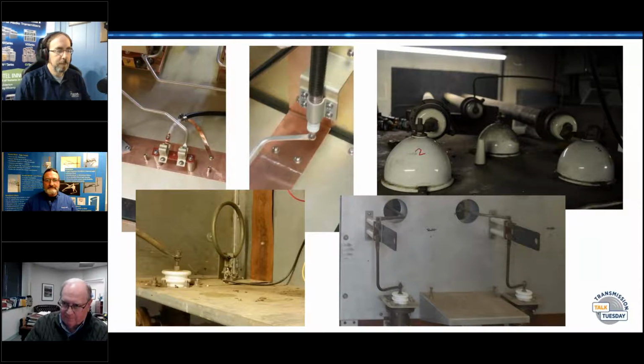That's why threaded connections inside ceramic insulators can sometimes cause trouble, because the sharp edges will start corona and crack the insulators. Chris mentions in the comments he once heard 6 ball gaps snap in stereo, and that was his cue to get out of there. Run like hell - I maybe paraphrased a little, but yeah, you got a lot closer to it.